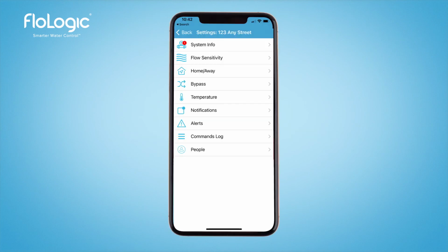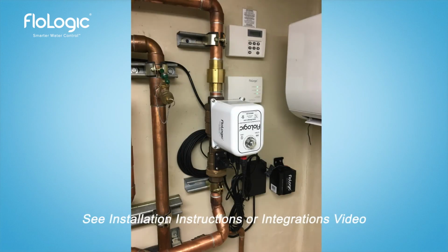With the installation complete, you can customize the settings if needed. Note that the default home flow time allowance is 30 minutes, the default away flow time allowance is 30 seconds, and the default flow sensitivity is 2 ounces per minute. Refer to the FloLogic installation instructions for more details and technical information about the installation and programming process.